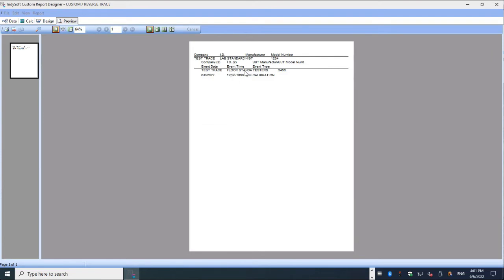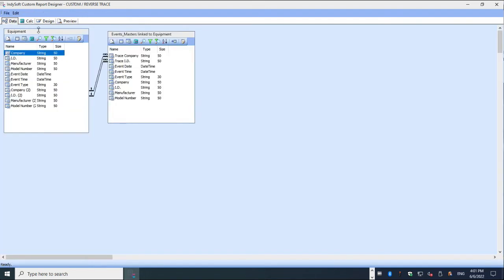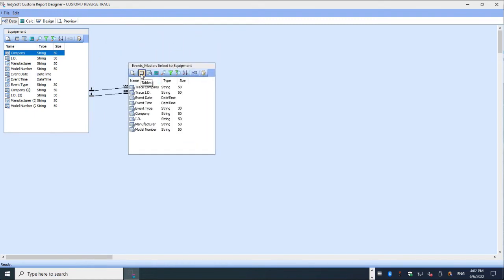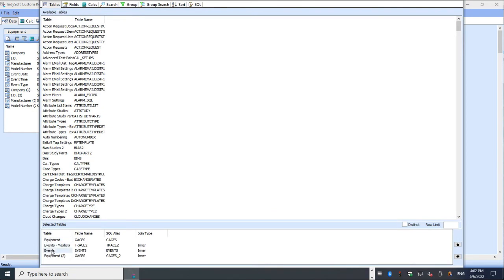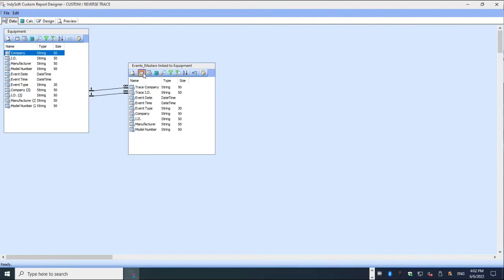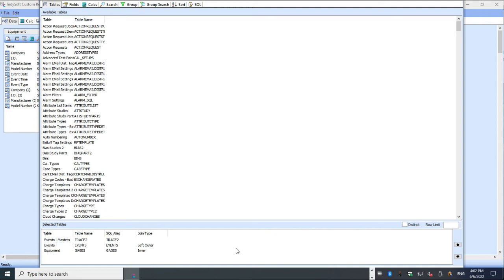However, since this floor standard is in and of itself a master, we now have another problem, which is what all did it calibrate? Because the lab standard is out, the floor standard calibration may be invalid, and we may want to know the full scope. So here, I'm going to take this event masters, and it's almost the same thing. For the equipment, I had equipment, events, masters, events, equipment. Here, I've got events, masters, events, equipment.